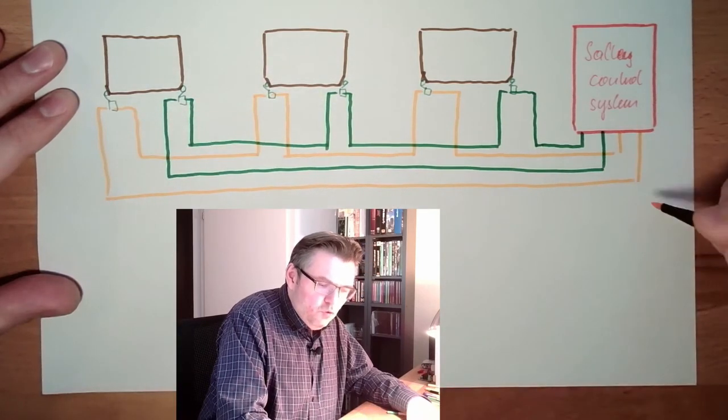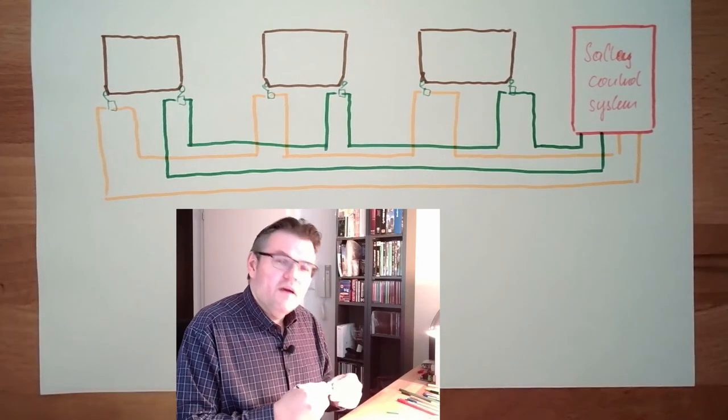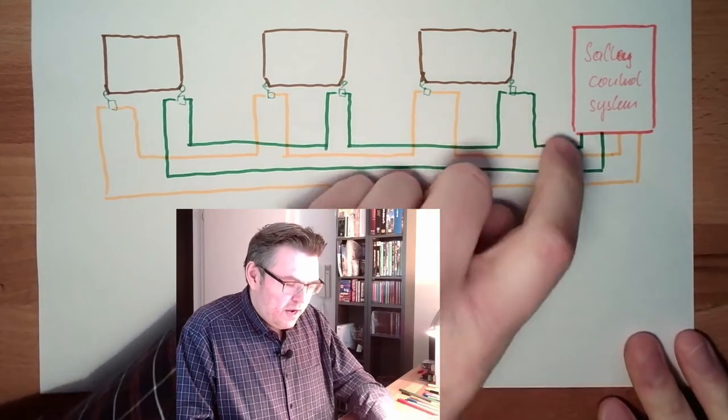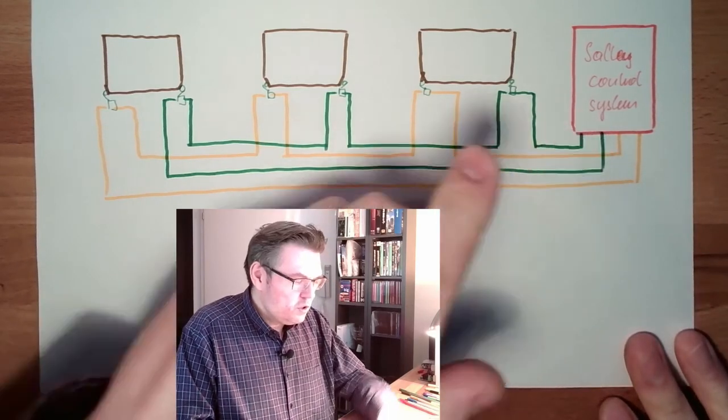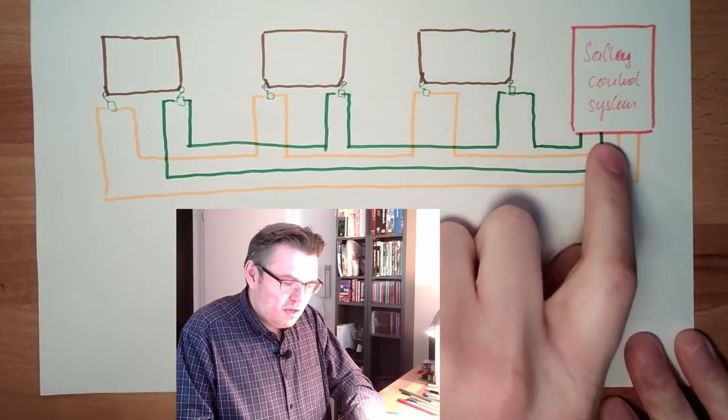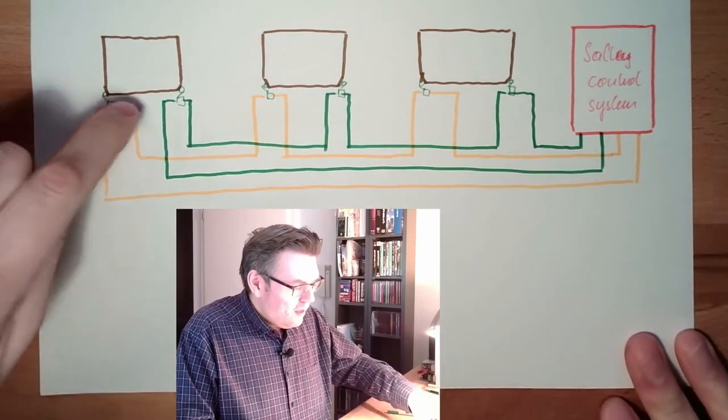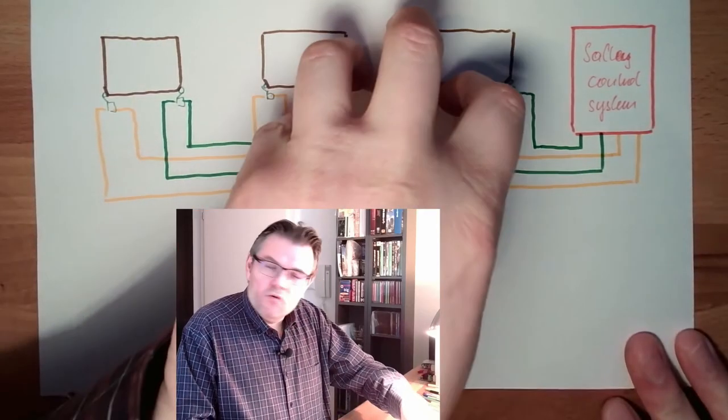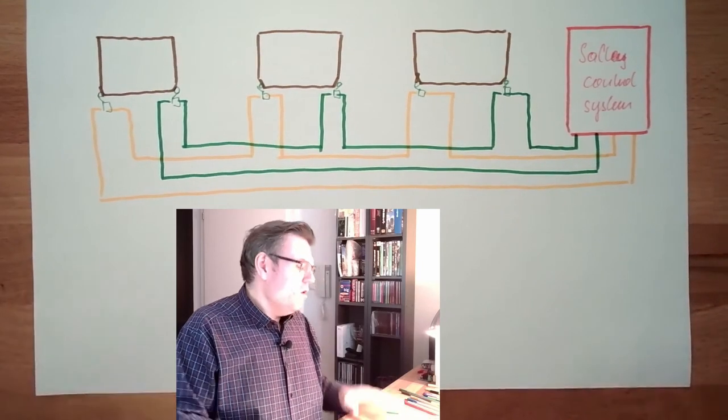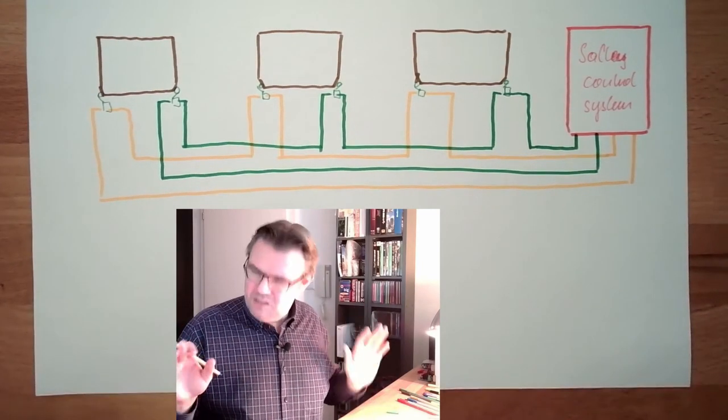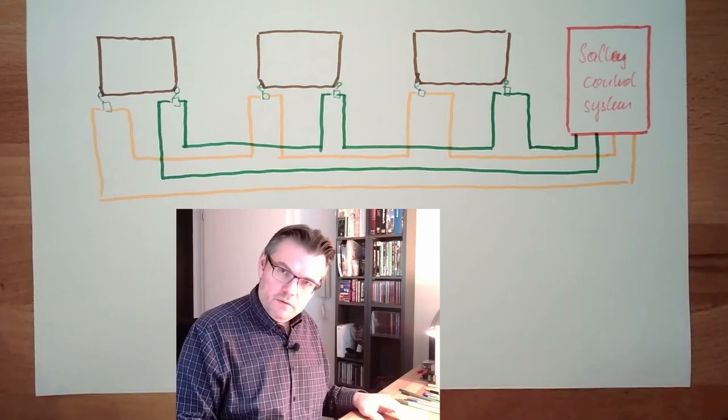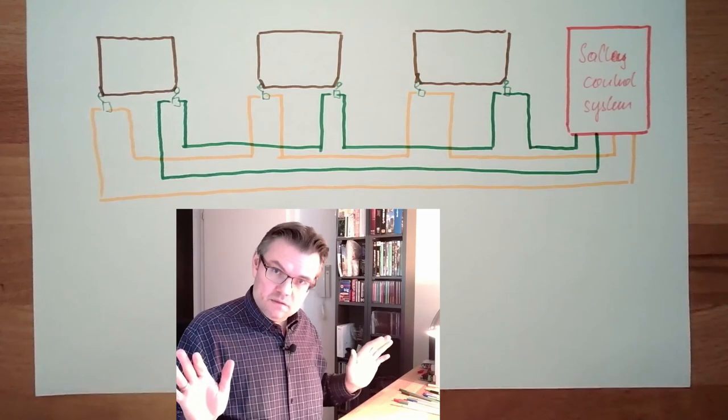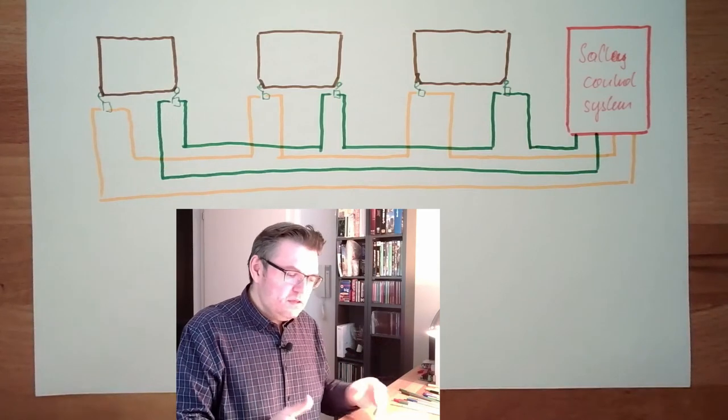Now I have two loops. Now I have two loops, and they are usually active high. So this means if here is a voltage and I can get back a voltage, the doors are closed. If here is a voltage, I get back the voltage, then the left switches are indicating the doors are closed. And if all switches are indicating the doors are closed, I can, the safety control says, okay, if you want to start, you can start. Gives the permission to start the machinery. If then one of these open, the permission is canceled. So this is how this is working.